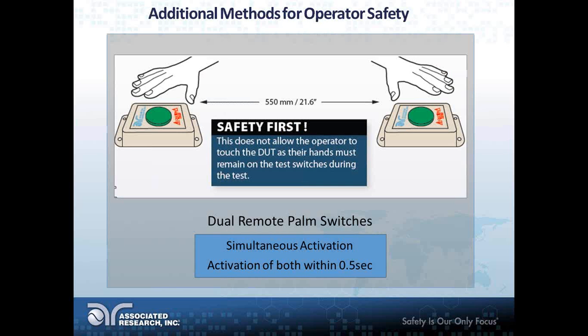You have to simultaneously activate the buttons, or they have to be activated within 0.5 seconds of each other, and your hands have to remain on the buttons the entire time you're testing. If one hand comes off either button, the test will stop. That's the way you want it, because then the operator cannot have a free hand. This is especially helpful if you cannot have a DUT enclosure, because the operator can't touch it—if their hands have to stay on the buttons, they can't touch the DUT.